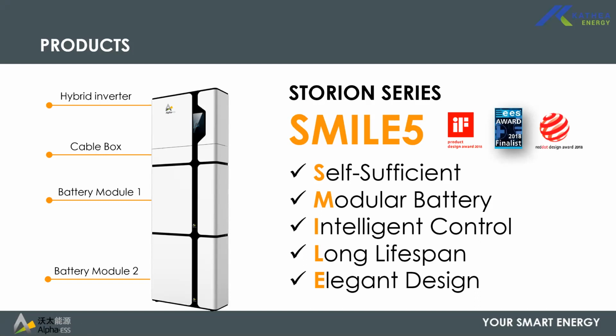And also on the cable box, you come with pre-installed protection and isolation devices. So you get your breakers pre-installed. So with this system, there is no need for extra protection and isolation of the DC and AC inputs together with the outputs as well. And then the two modules below, those are the battery modules. They're basically designed for a Smile 5. So the system is a plug and play system. Everything is pre-configured from the BMS. There is no need for you to get different cables and all that. It's a matter of setting it up and just plugging the right cables at the right place. All cables are provided with the system.